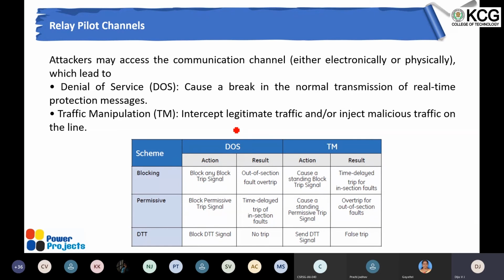That is nothing but the DTT scheme we already have seen: when a fault is seen in zone 1, it gives a signal to the other end relay, and it operates. The last one is exactly the one we have discussed, so I'll try to explain with DTT. If somebody breaks that communication cable, that is denial of service, nothing but a break in the cable. In that case, no information comes back from the other end. So even though the relay is required to operate immediately, like if the fault is at a location after 80%, where it is supposed to operate instantaneously, because of the break in the system it cannot operate. So it goes for the 400 millisecond time-delayed operation. This is one of the risks.